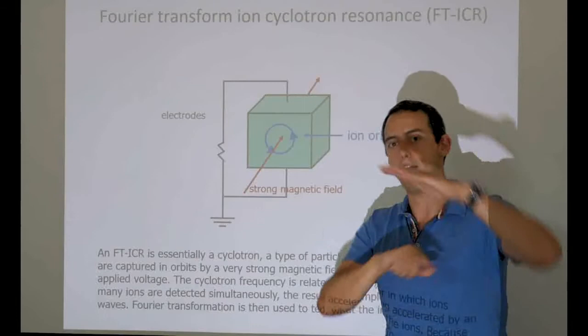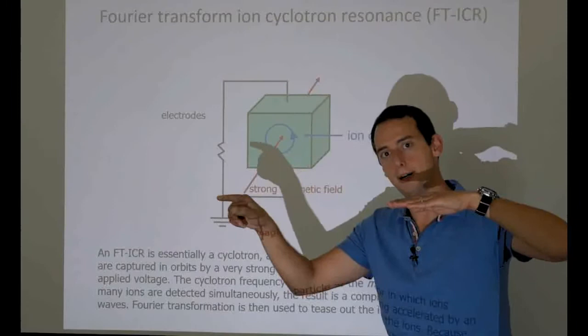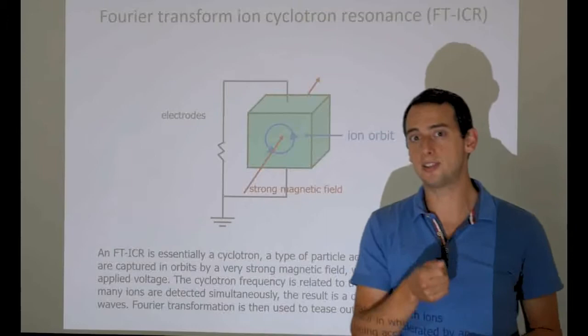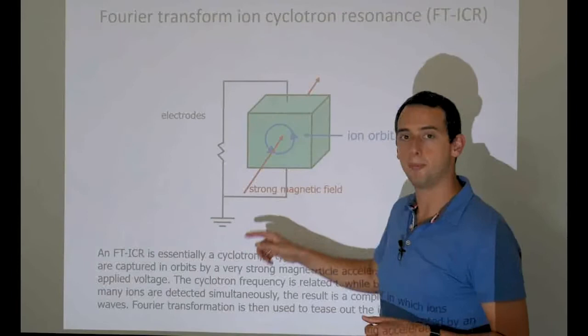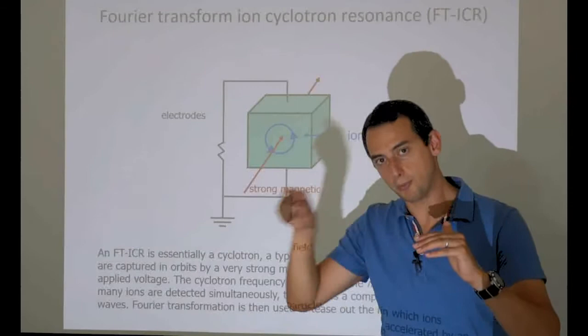Every time the ion passes, it gives off a little spike. If the ion goes really fast, there will be lots of spikes; if it goes slow, there will be fewer, more widely spaced spikes. So the speed with which the ion moves—which is related to the kinetic energy and the mass of the molecule—can be read out from the spike distance at the electrodes. The electrodes measure the time it takes for an ion to complete an orbit.